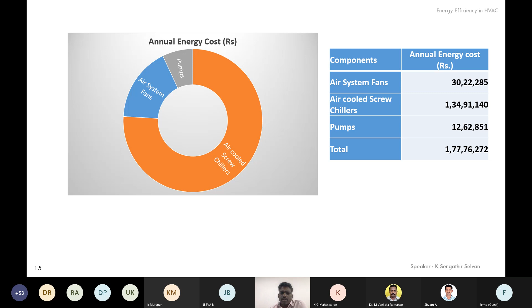Now, with the screw chillers, you can see 70 or 80% of our energy consumption in a commercial building goes to the chillers, and the pumps are generally around 5 to 6% of our total HVAC energy consumption. The pumps are only for circulating the chilled water from the generating point, that is the chiller, to the load, that is the air handling units. In the air handling unit, it's like the indoor unit of your split unit. It will have a cooling coil and a fan inside. So the fan consumption is considerable here. It is higher than the pumps, mainly because the specific heat of air is 4 times lower than water, so we need a lot of air to transport the cooling energy from the chilled water to the air. Actually, you can see that correlation.